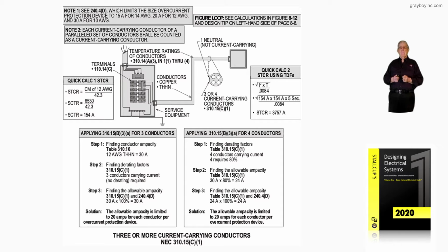They're number 8. But they're routed through an ambient of 125 degrees Fahrenheit. So we basically have exceeded 10 foot or 10% of that run, or where the authority having jurisdiction permits 10% of the overall run. Now, step 1, 125 degrees Fahrenheit, requires a 76% derate in accordance with table 310.15B1 based upon THHN insulation routed through an ambient of 125 degrees Fahrenheit, 90 degree column.